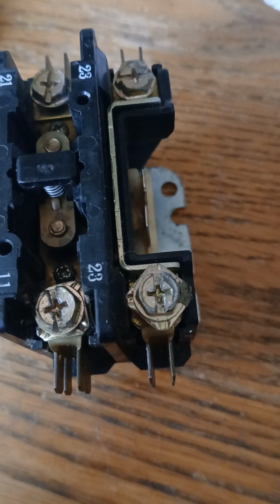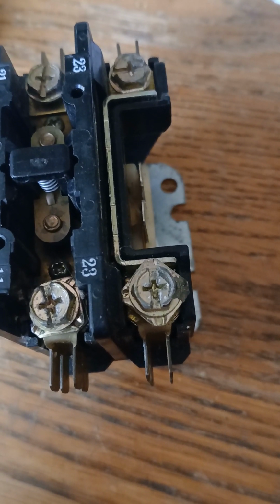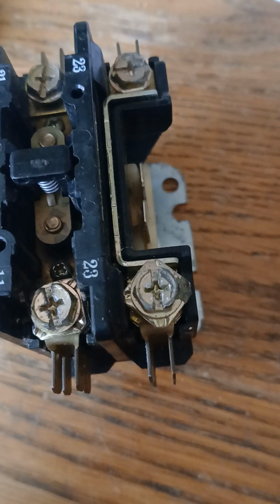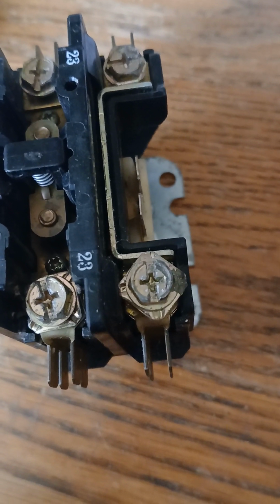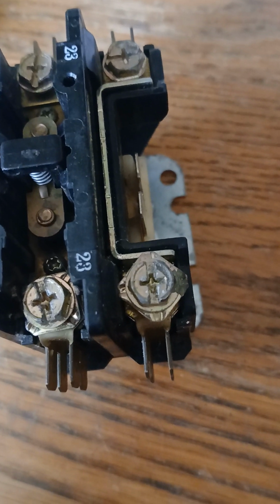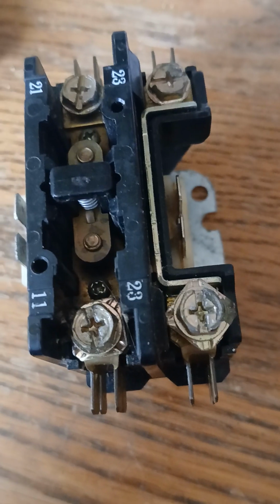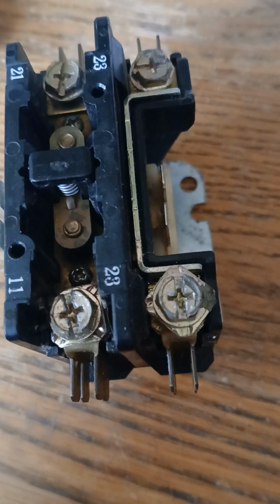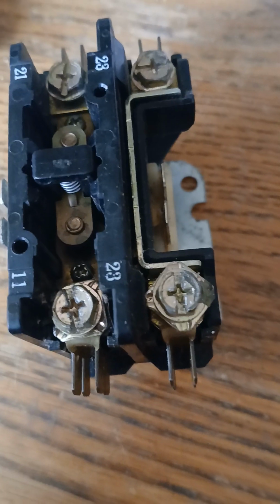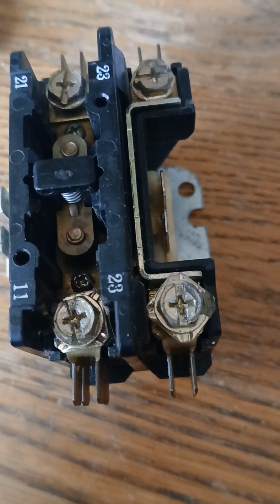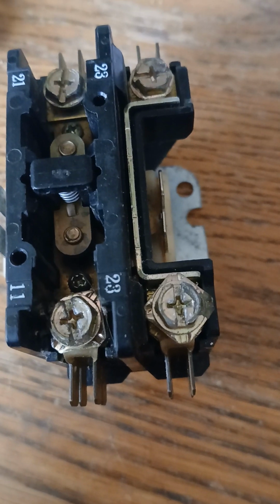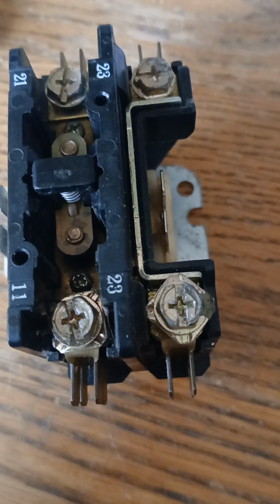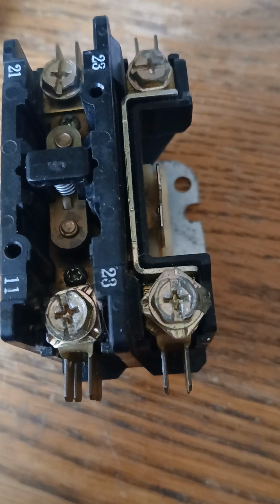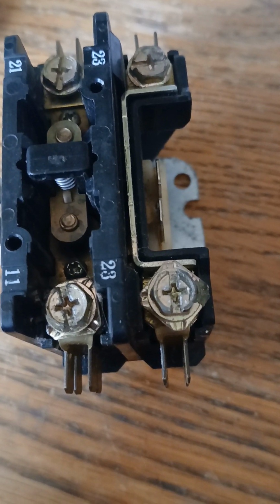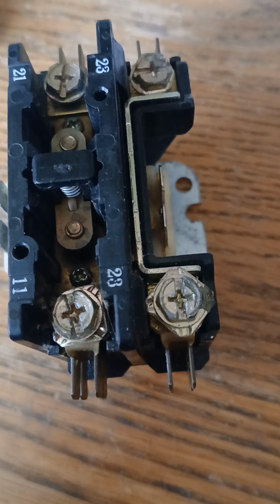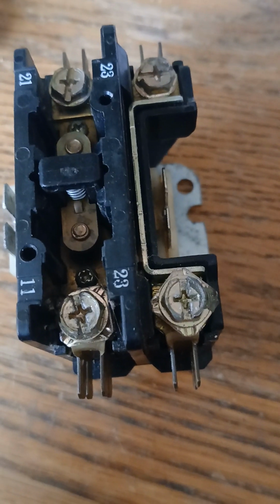What we would need to do is energize the compressor and the condenser fan motor, and then inside the blower motor would need to be energized. This would blow the air through the ductwork and through the registers in the house. And outside at the condenser are the compressor and the condenser fan motor. Note the term condenser fan motor, not blower motor. The condenser fan motor outside.